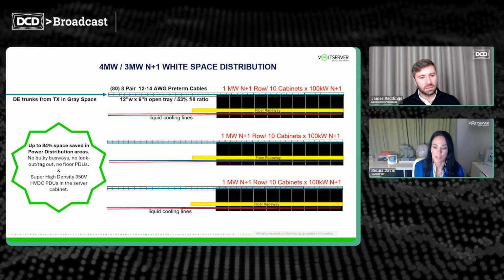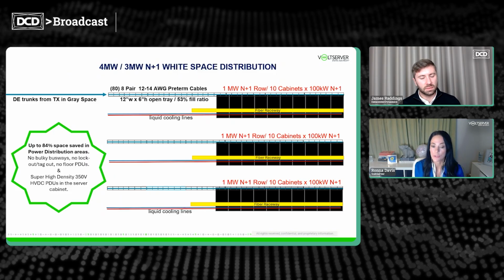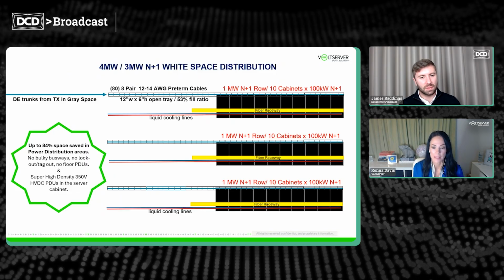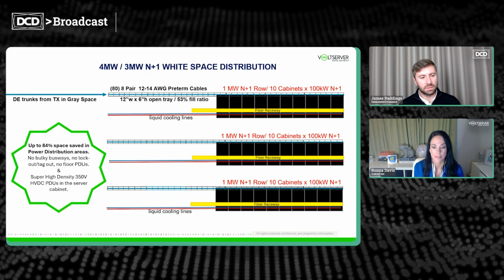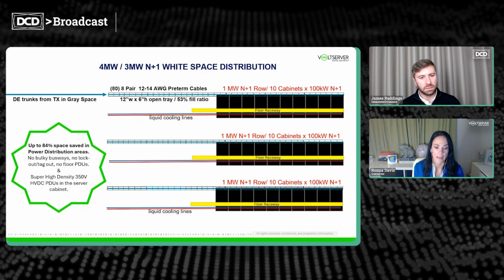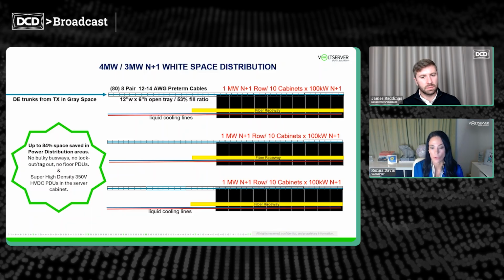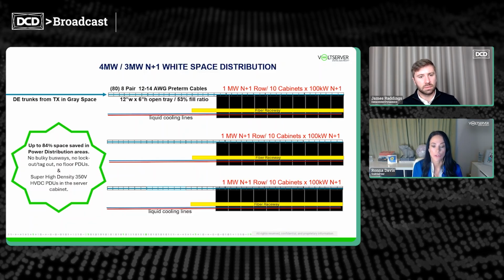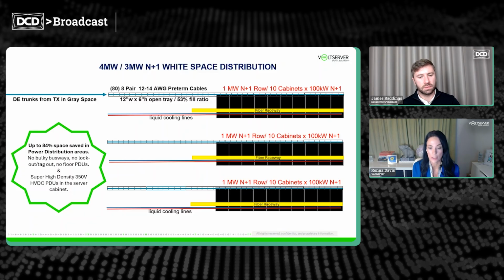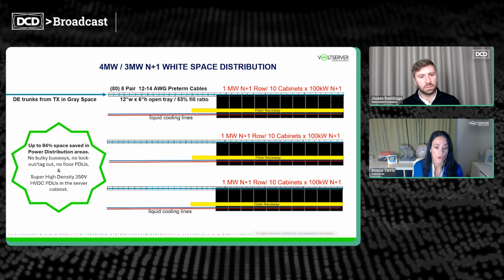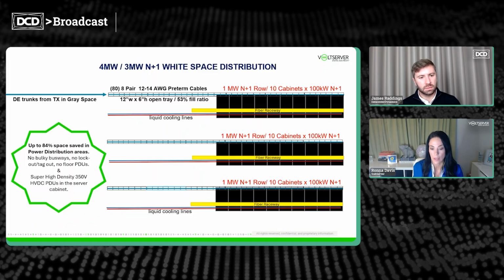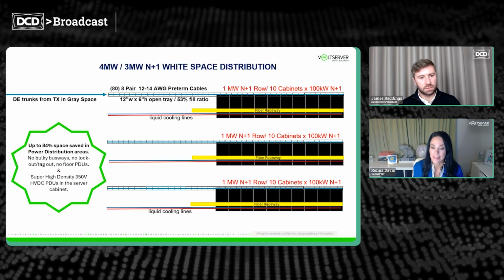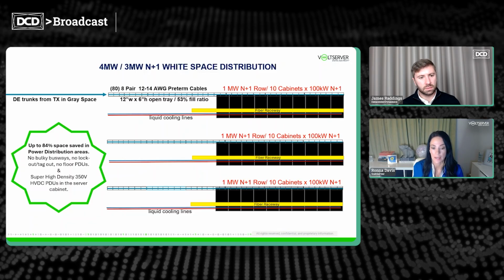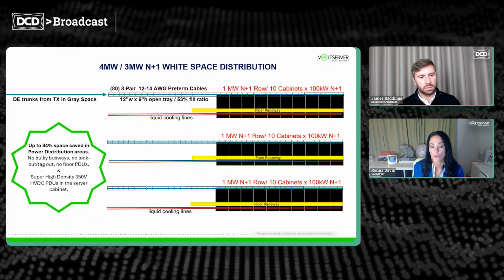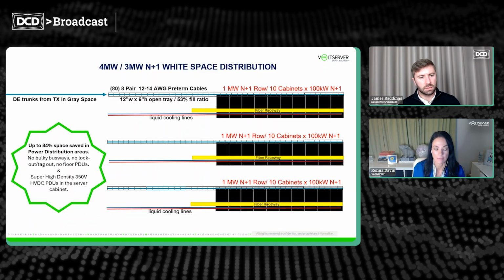But from the gray space, you have open basket tray with those UTP cables feeding each server cabinet that is powered at 100 kilowatts N+1. All that space that you have recaptured from not using busways or having to have floor PDUs can be used to load up more GPUs in your clusters, both up and down and side to side. Additionally, you're going to have space to run your liquid cooling lines. In the compute area, DE can save up to 84% of space over AC systems at these same power levels.